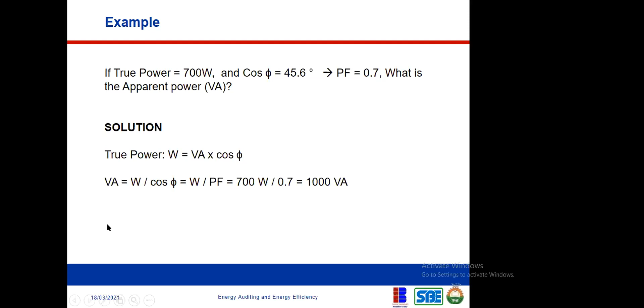In terms of kVA or VA, because that's how generators are rated in the market. Exactly, that's a good one. So when you hear generator ratings like 1000 kVA, that's the apparent power, not the true power it can deliver. If you're using that 1000 kVA to power a resistive load, your power factor is 1. But if it's not a resistive load, you have to consider your power factor, which introduces waste. Yes, that's what it means. Thank you very much, Engineer.